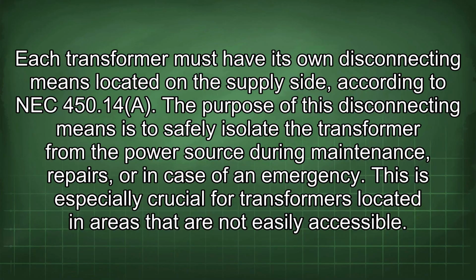Each transformer must have its own disconnecting means located on the supply side, according to NEC 450.14(a). The purpose of this disconnecting means is to safely isolate the transformer from the power source during maintenance, repairs, or in case of an emergency. This is especially crucial for transformers located in areas that are not easily accessible.